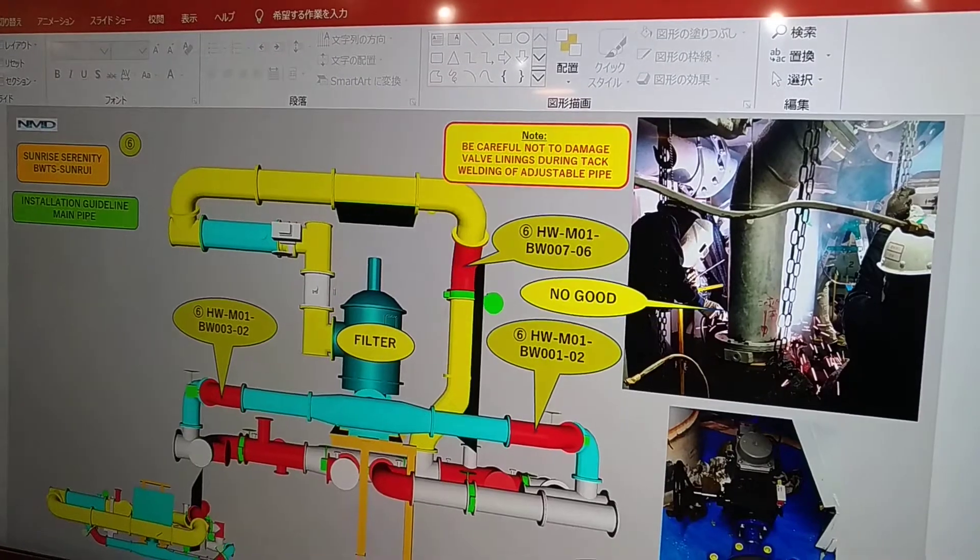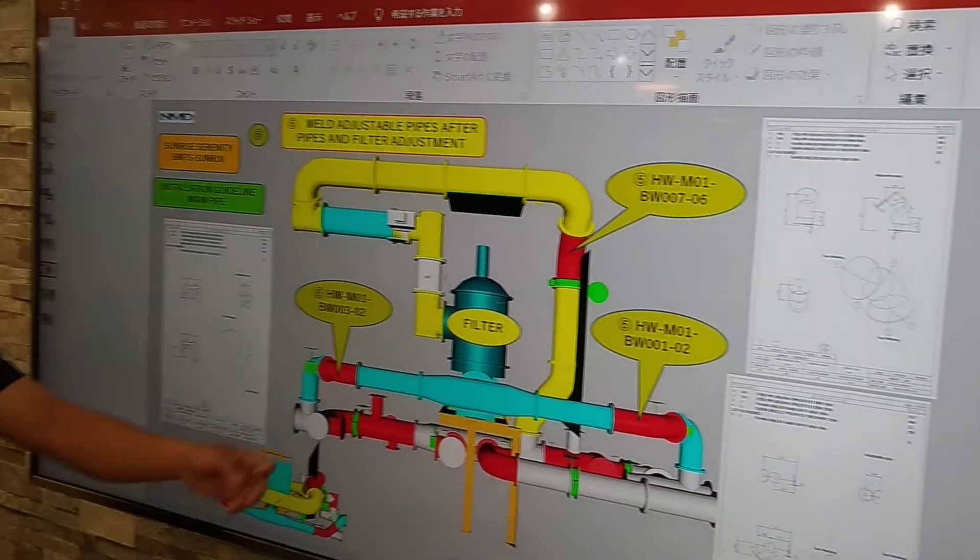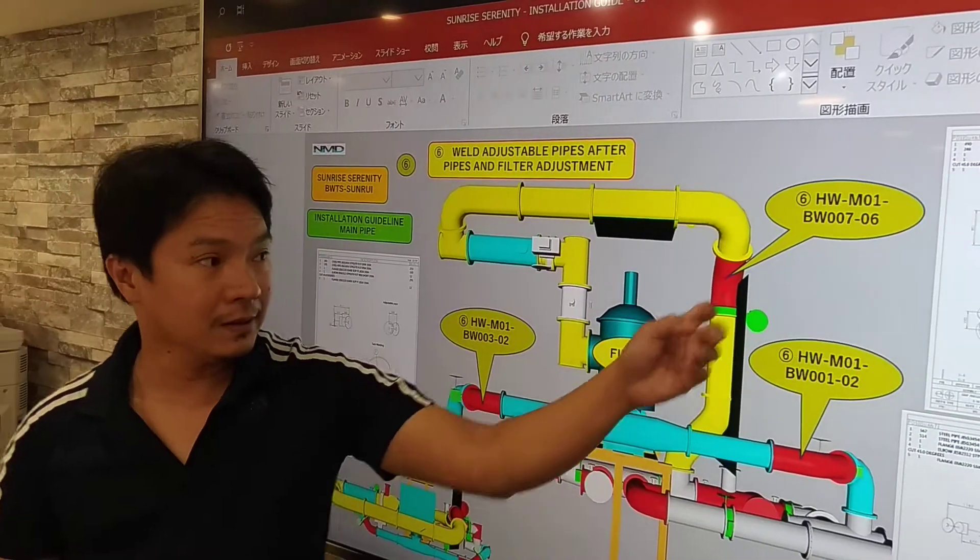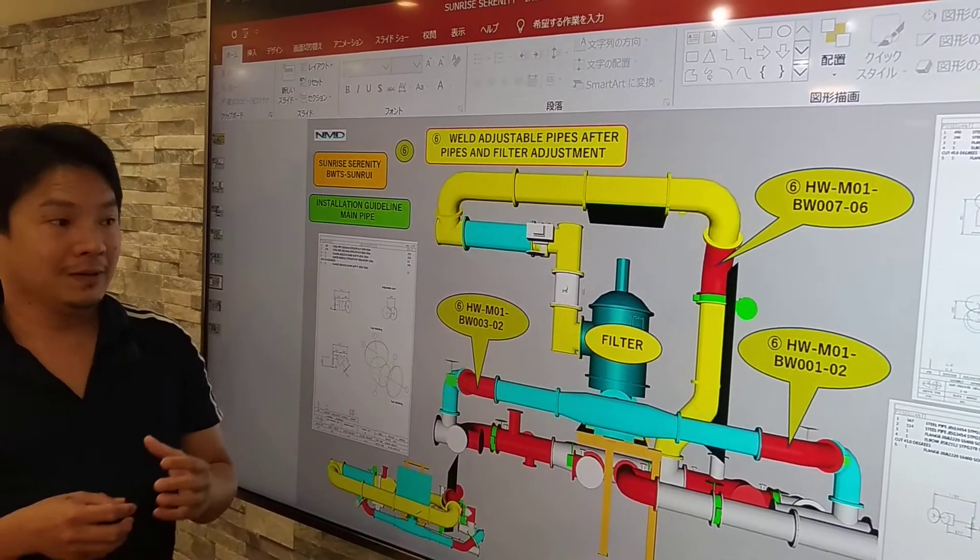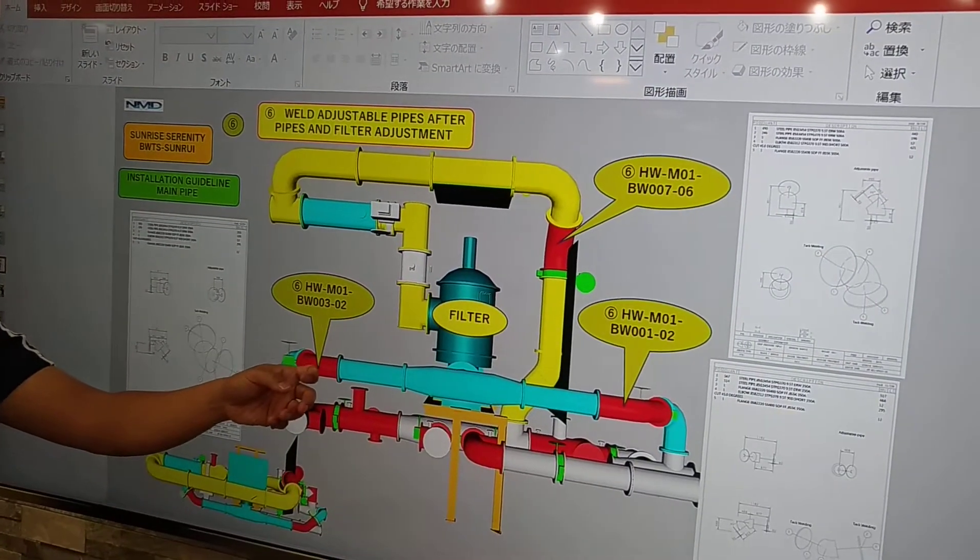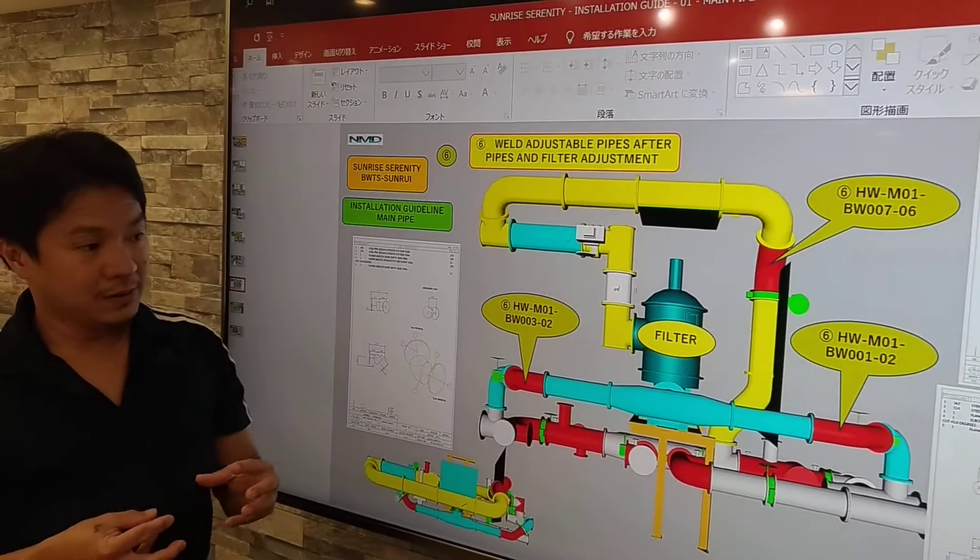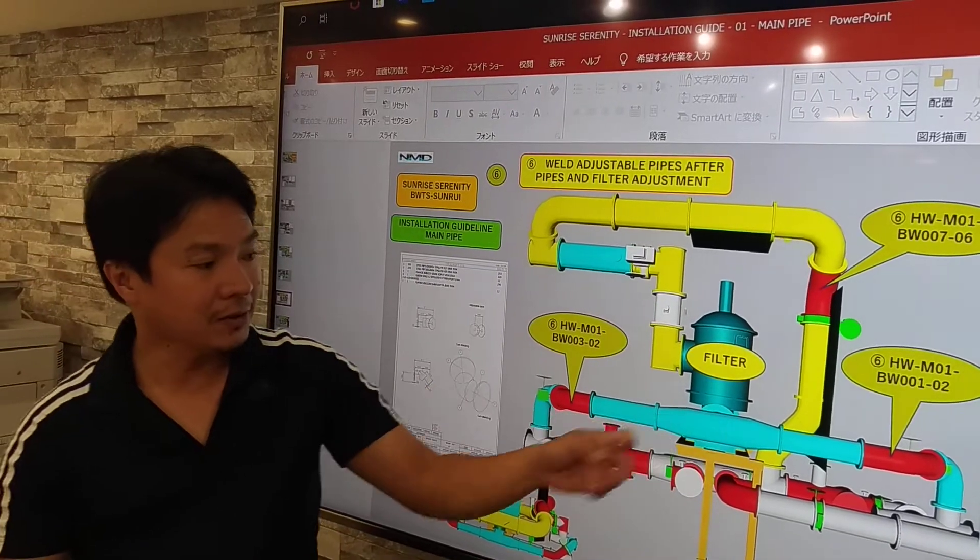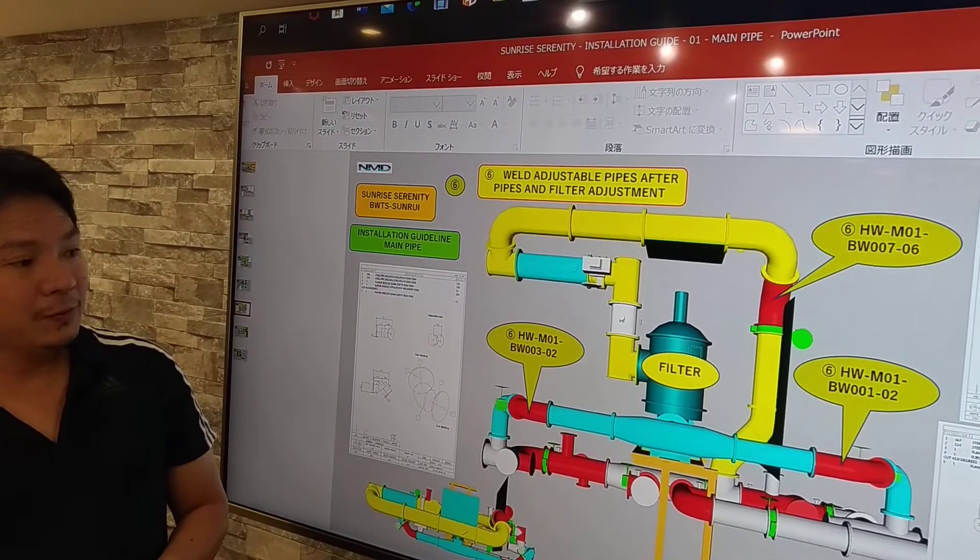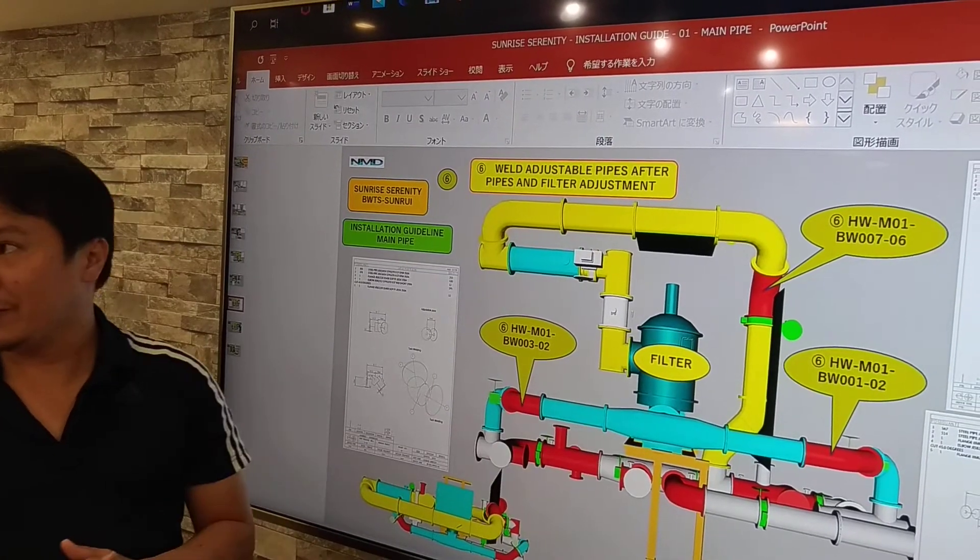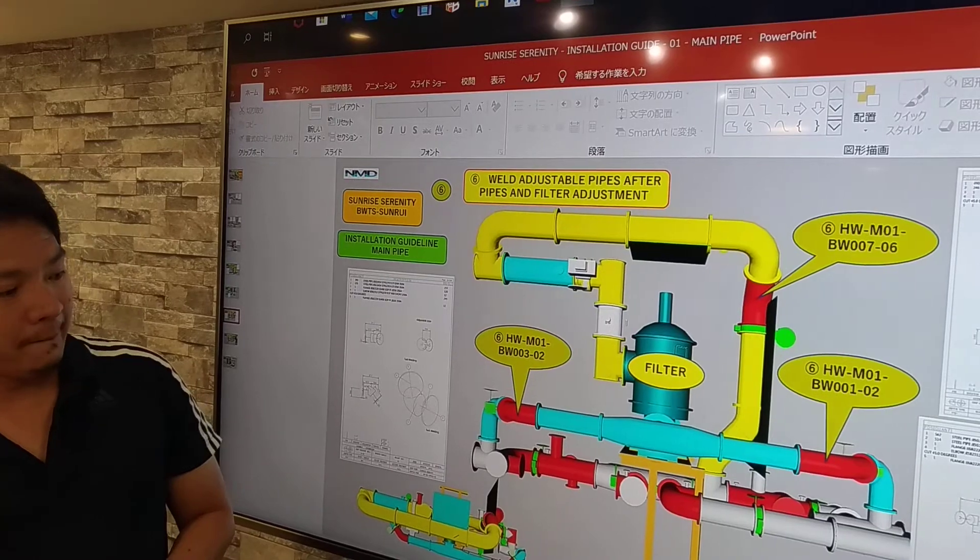So next is we have to install now the adjustable pipes. So always don't put pressure on the pipe. Always use the adjustable pipe to keep the pipes not on pressure. So if we put pressure on the pipes, we will have problem during operation. Maybe some leak during operation.